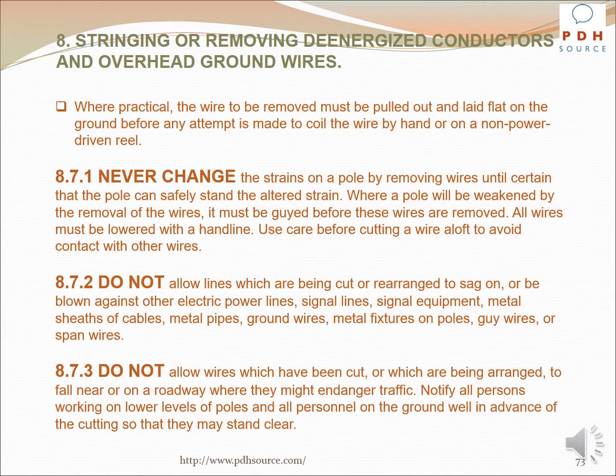Use care before cutting a wire aloft to avoid contact with other wires. Do not allow lines which are being cut or rearranged to sag on or be blown against other electric power lines, signal equipment, metal sheaths of cables, metal pipes, ground wires, metal fixtures on poles, guy wires, or span wires. Do not allow wires which have been cut or which are being arranged to fall near or on a roadway where they might endanger traffic. Notify all persons working on lower levels of poles and all personnel on the ground well in advance of the cutting so that they may stand clear.